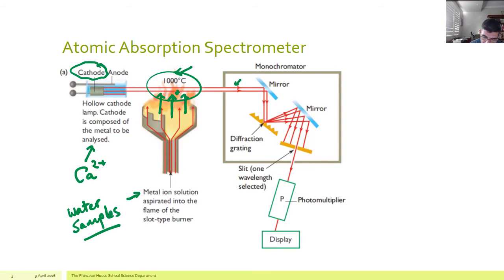So the light passes through from the cathode. It passes through the vaporized gases. Some of that energy has been absorbed at particular wavelengths. And then through a series of mirrors and diffraction gratings, a specific wavelength will emerge, just the one. And that's why it's called a monochromator, which means one color, basically.